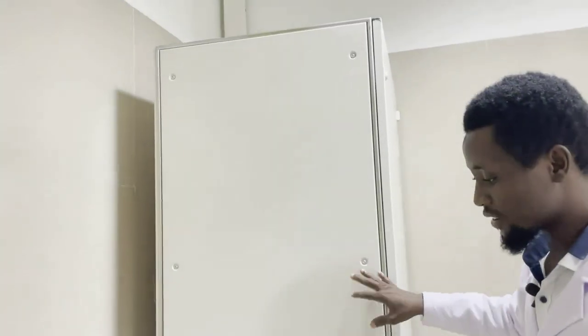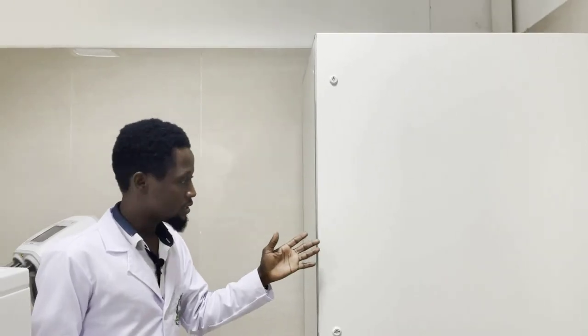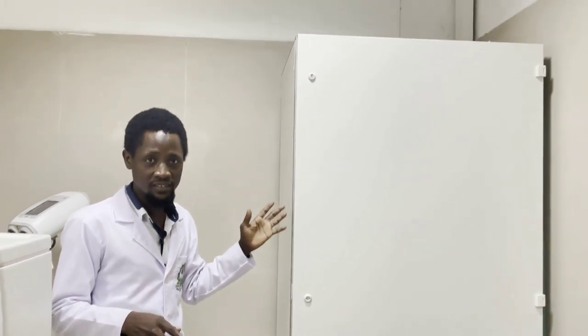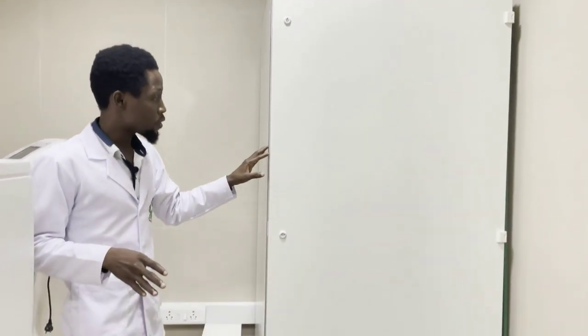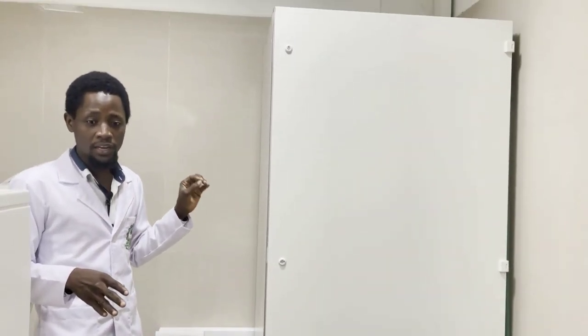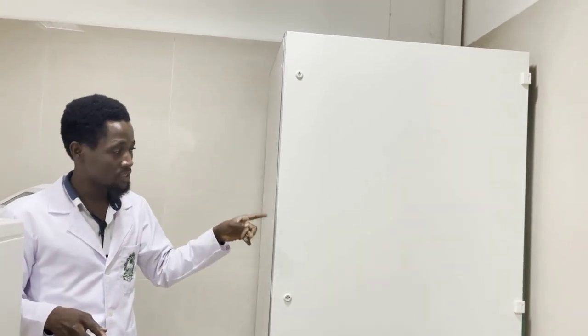When we move further, there is a bigger box compared to the image reconstruction box. This box is what we call the power distribution unit. This box can supply up to 565 volts DC, and an inverter for the X-ray generator is mounted inside this box. So these are the other components of CT.